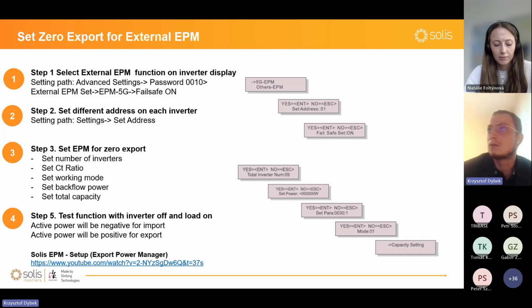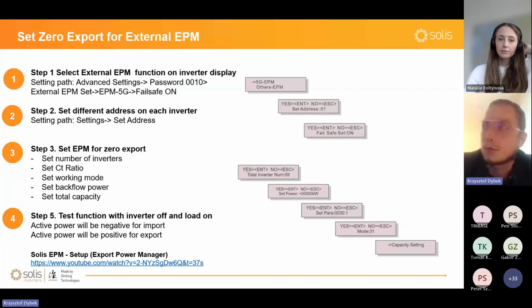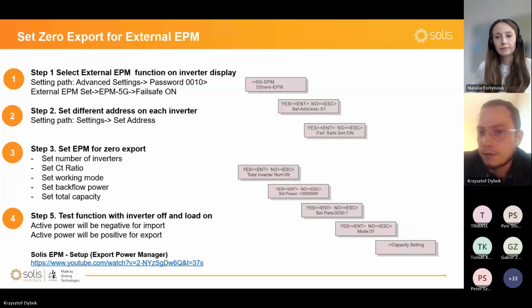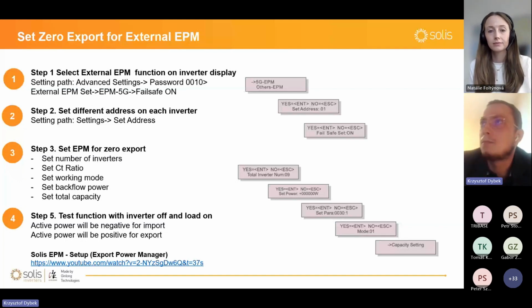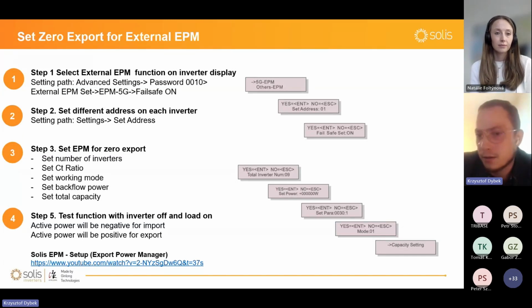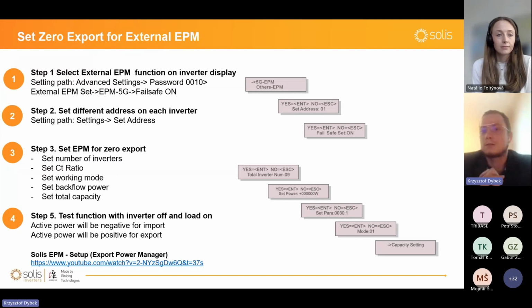Yeah, the second point is to set address. So you just go to settings and set a different address for each inverter. You start with 01, then go to another 02, 03, and so on. After that, you can go directly to the EPM device and set EPM for 0 export. So set number of inverters. This is easy: how many inverters you have in the cascading scenario. Then you should set CT ratio. Remember that secondary current here is 1, not 5.